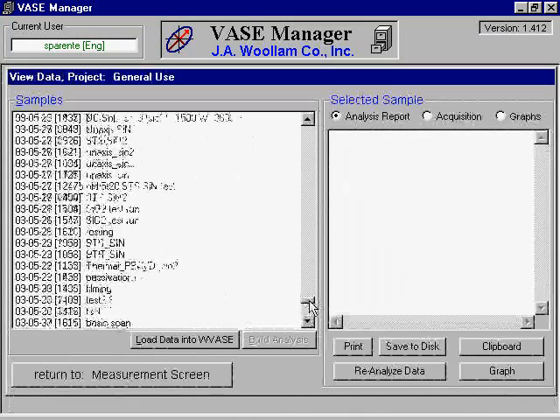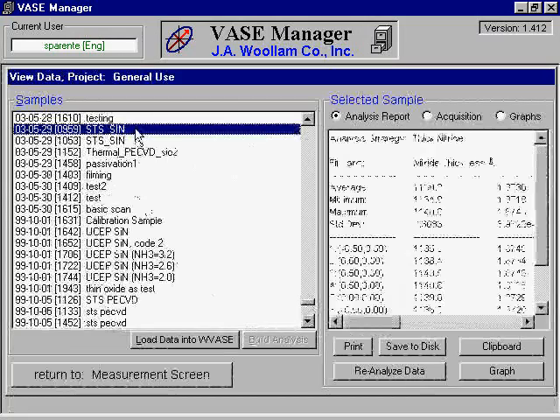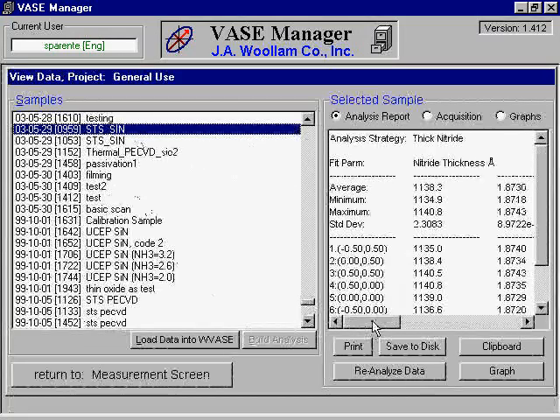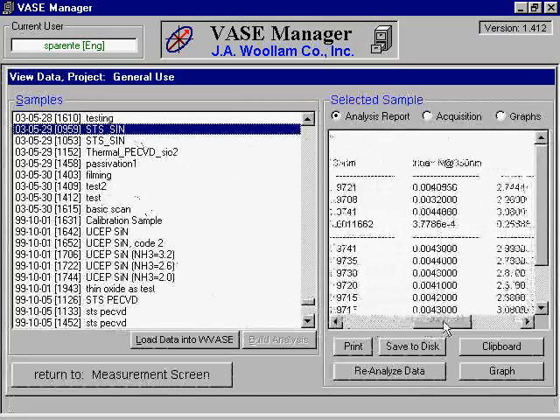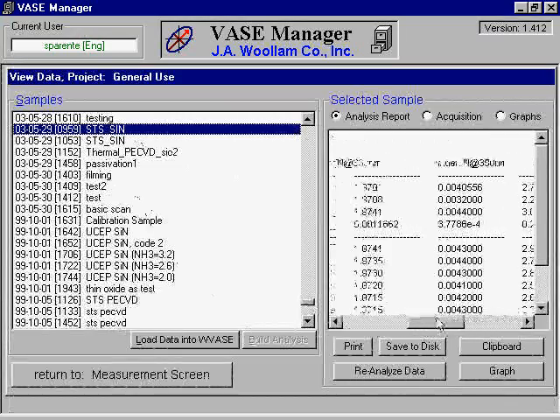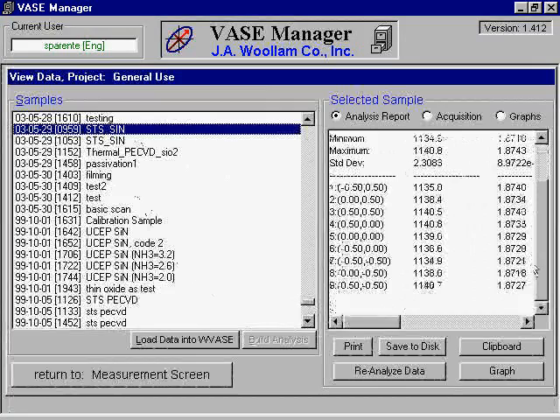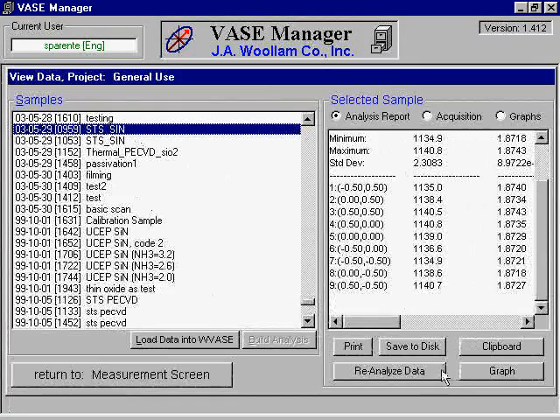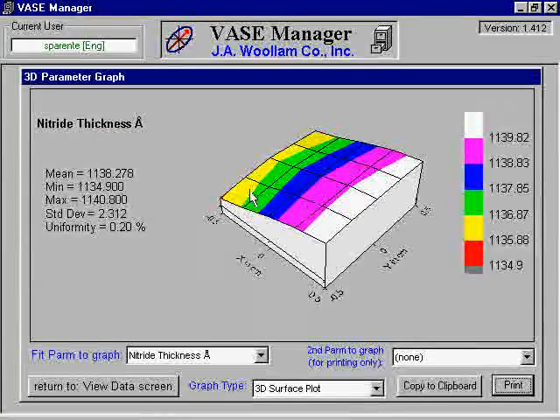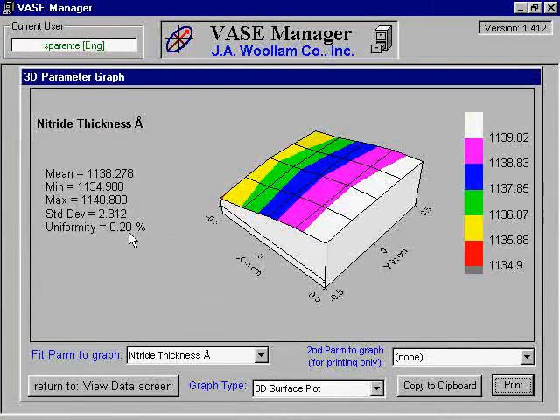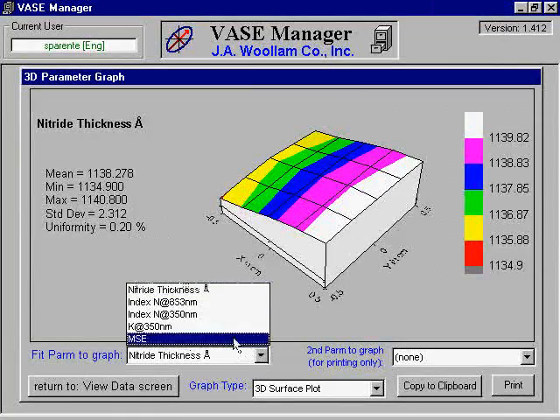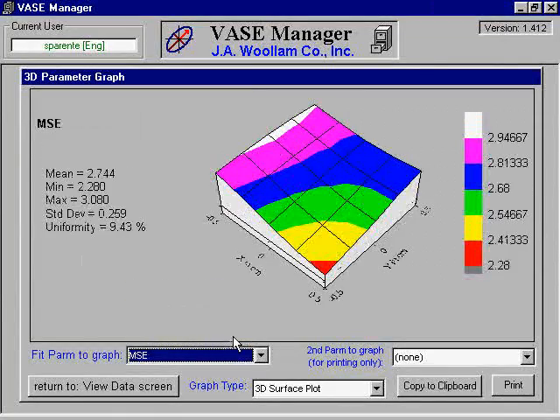In the Samples box, select the sample you wish to view. The samples are organized by date and labeled by the description you previously entered. Once selected, the results are shown in the text box on the right side. Data for all analyzed points, as well as the statistical data of the points, are shown. Clicking the graph button at the bottom will provide 3D graphs of different sample parameters and allow you to see how they change over the area of your sample. This graph can be most useful for viewing the uniformity of your sample.